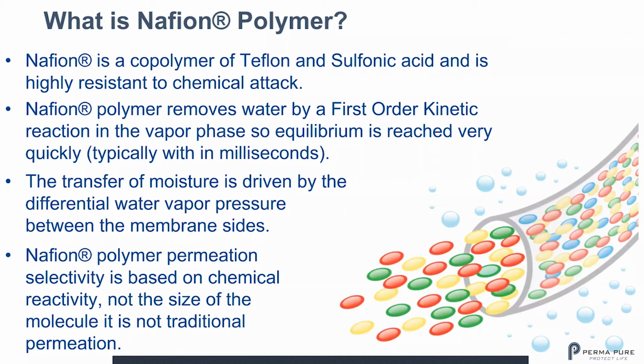And this diagram at the right shows you how it works. So in this diagram, you have the flow moving from right to left, coming out of the tube. You see the blue spheres in the tube, and outside of the tube represent the water being removed from the sample gas. And what's left over is the red, green, and yellow components. Those are the ones that you want to measure. So the way the water transfers through the material is unique. It's what makes Nafion unique, that it is a chemical reaction with the surface, and then the water becomes part of the material's structure, and the water moves through the lattice, through the material, from one side to the other, based upon the relative vapor pressure differential of water.